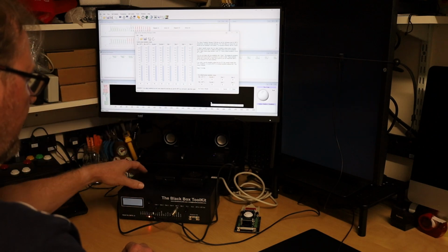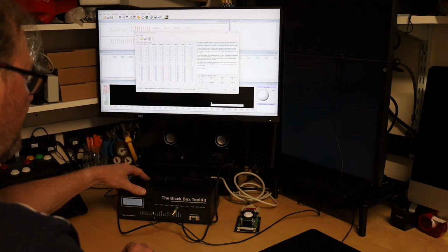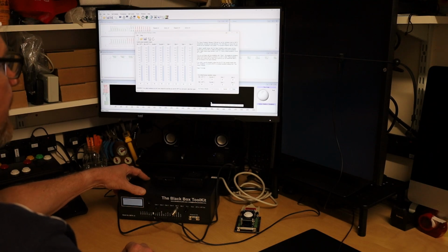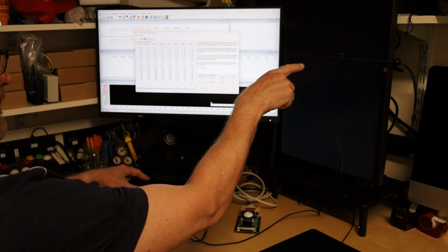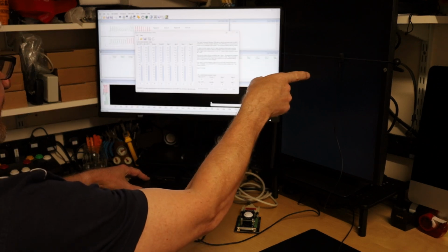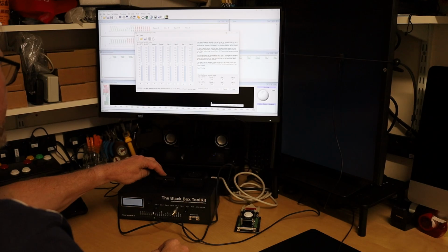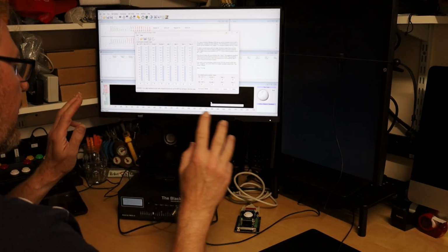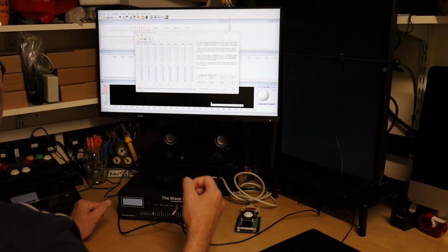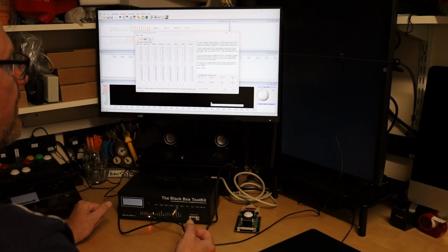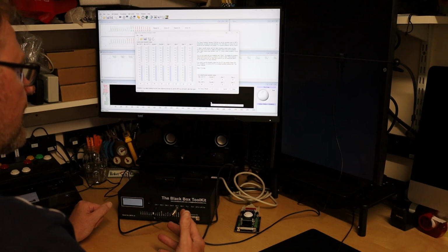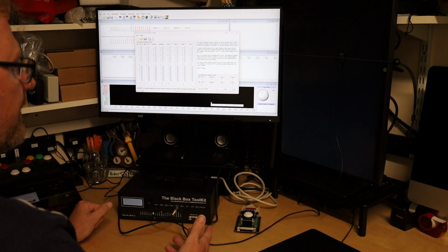You basically program the V3, and then once you set it running, it's completely independent of the PC, so it's not interacting with the PC at all, other than the sensors are looking for things on screen with the optos, the microphones are trying to detect things, the TTLs are detecting things. So it's completely separate from your PC, and then once it's finished capturing the data, it'll upload it to your PC, and then you can check it to make sure that your timing's accurate.